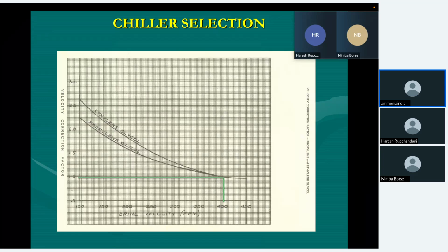So these are the chiller selection, ethylene glycol and propylene glycol velocity selections. Normally, since the glycols are viscous fluids, we don't stop at 250 fpm velocity like condenser or 300 fpm. We select an average velocity of 400 fpm, and at 400 fpm velocity, the velocity factor is 1. So normally the chillers are selected at 400 feet velocity. If you select lower velocity, your multiplier will go up. So your chiller size will become bigger.